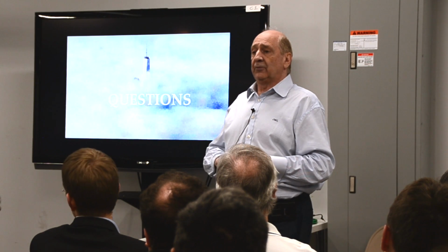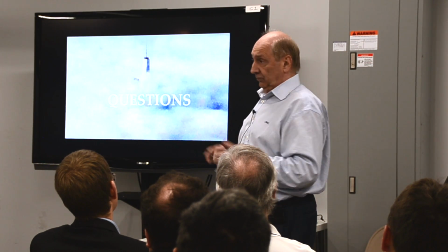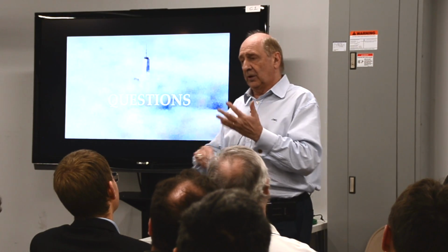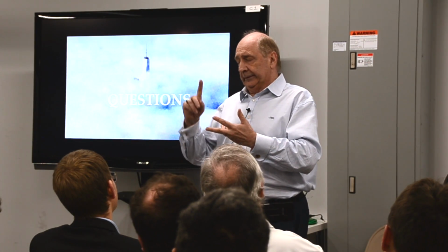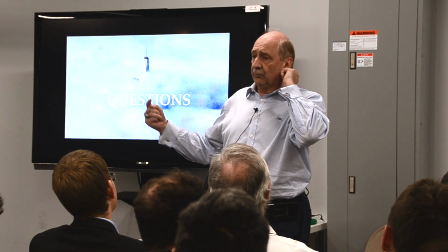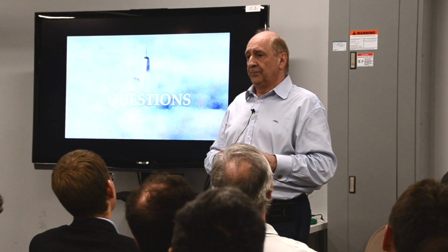How is the generator fueled? The generator is diesel. There are 2 10,000-gallon diesel tanks downstairs, in a submarine environment with bulkhead doors and all that. The generator is on the 6th floor, above grade. All the carriers, Verizon, Tower Stream, Time Warner Cable, anybody else coming in, comes from the manhole into the building below grade, up to the 6th floor. The point of presence room is on the 6th floor. There are no breaks in any cabling below that can be affected - we brought everything up to that point.